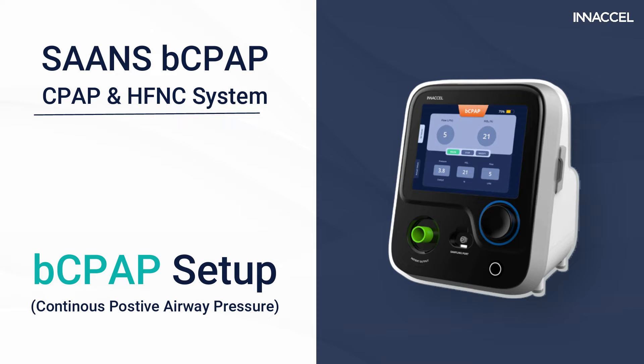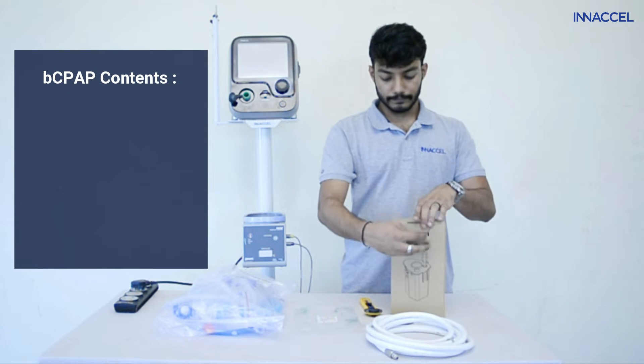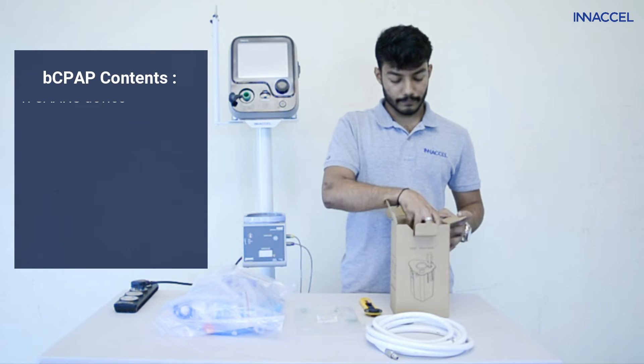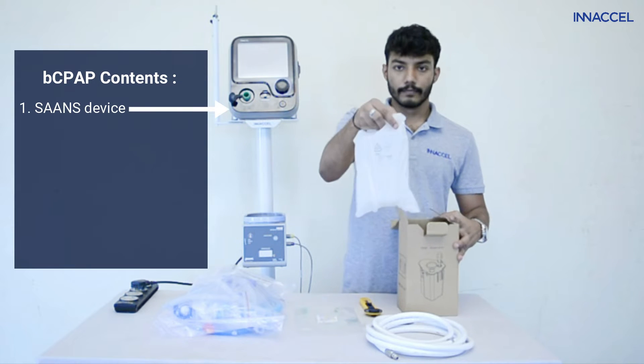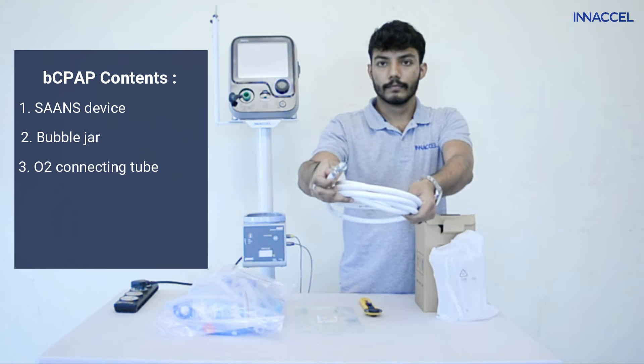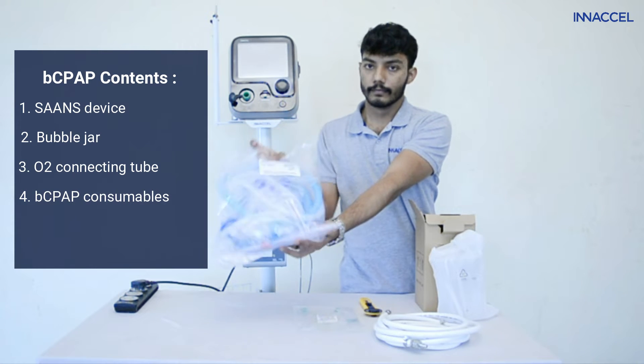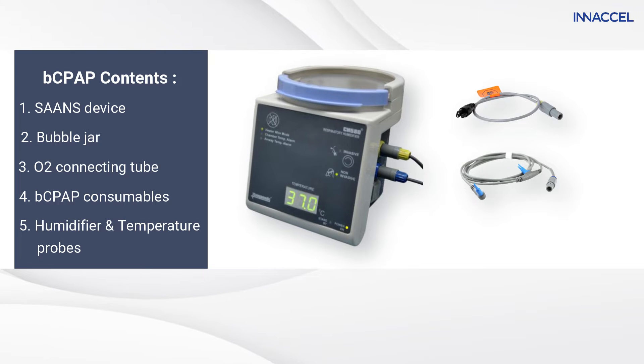Let us show you how to set up SAANS bubble CPAP mode. You primarily need 5 components to use SAANS in bubble CPAP mode: SAANS device, bubble jar, O2 connector tube, the consumables packet, and humidifier and temperature probes.